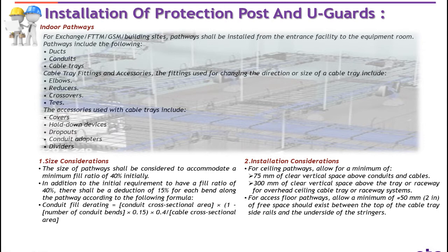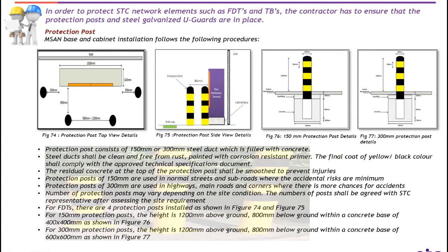Size considerations: the size of pathway shall be considered to accommodate a minimum fill ratio of 40% initially. In addition to the initial requirement of 40% fill ratio, there shall be a deduction of 15% for each bend along the pathway according to the formula: Conduit fill derating = conduit cross-section area × (1 − number of conduit bends × 0.15) × 0.4 ÷ cable cross-section area. Installation considerations: allow a minimum of 75 mm of clear vertical space above conduits and cables, and 300 mm of clear vertical space above the tray for overhead ceiling cable tray systems. For access floor pathways, allow a minimum of 50 mm of free space between the top of the cable tray side rails and the underside of the stringers.